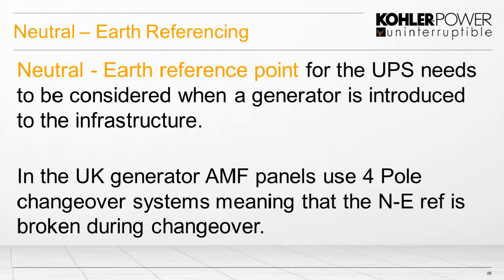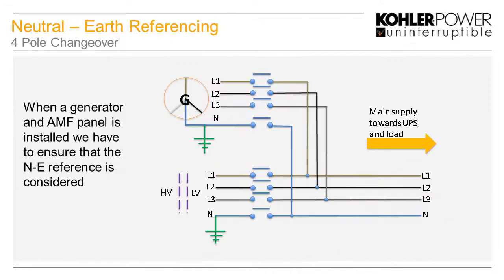Now, another thing that we get asked about is neutral earthing, especially when we have UPSs in. So we have to consider it. In the UK, we typically have to use 4-pole changeovers. And what that means is that during the changeover between mains and generator and vice versa, we will have a time when the neutral earth is not connected and it's not referenced together.